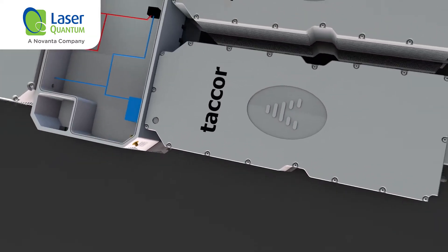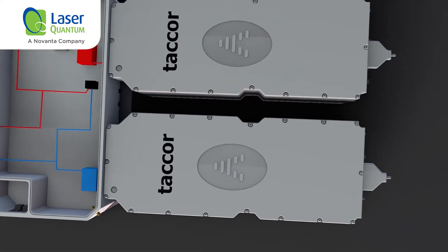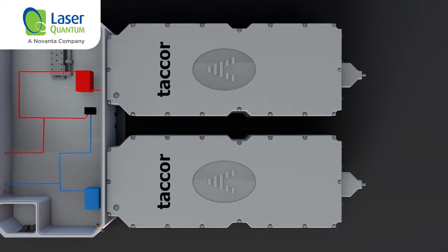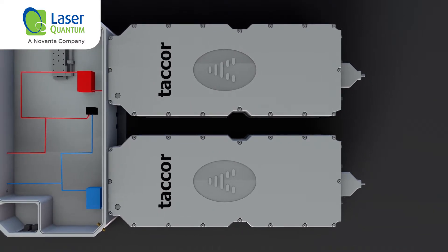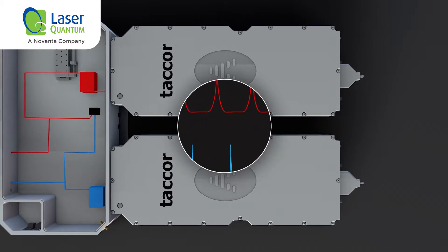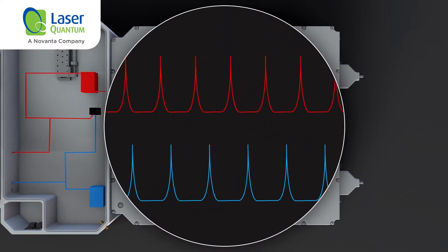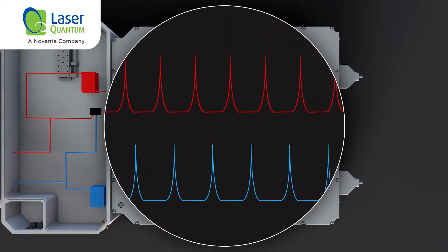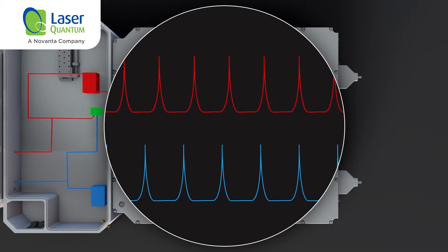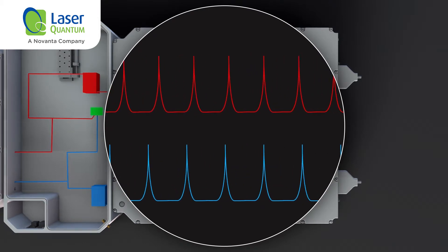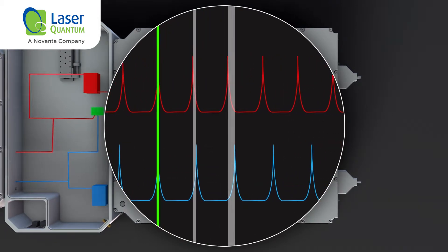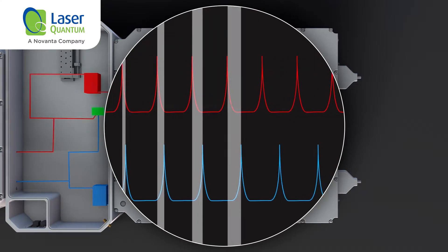Using the TL-1000 ASOPS repetition rate offset stabilization unit permits time-domain spectroscopy with unprecedented accuracy and resolution. The optical triggering unit generates the measurement start, where the pump and probe pulses are synchronized.